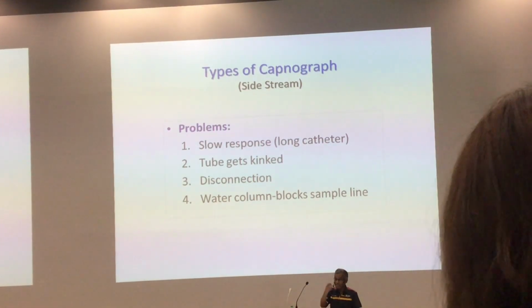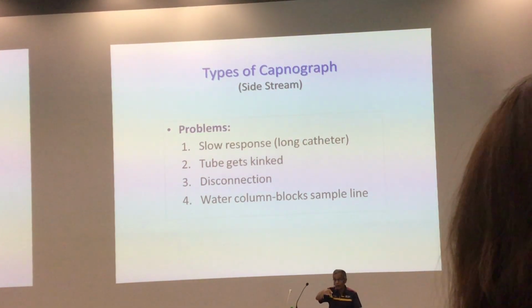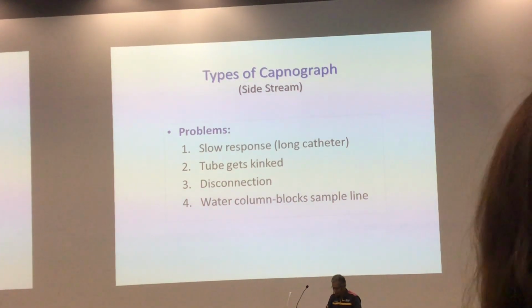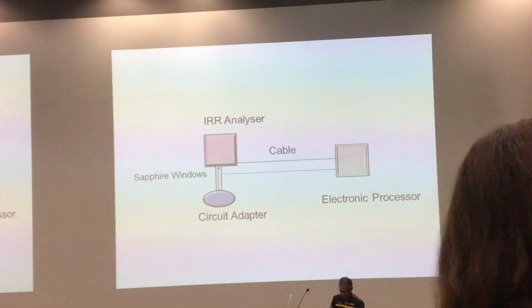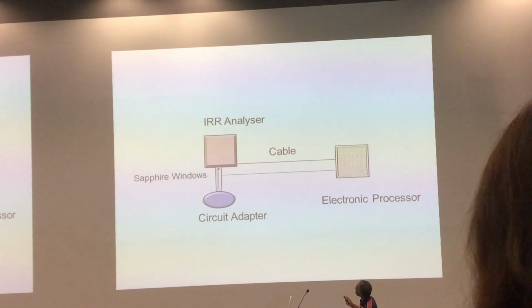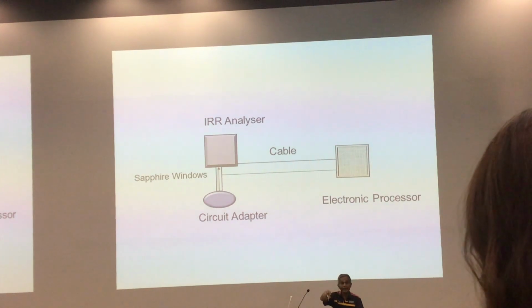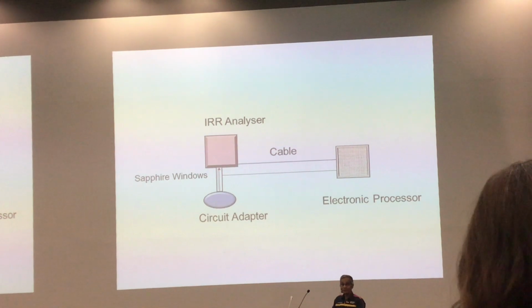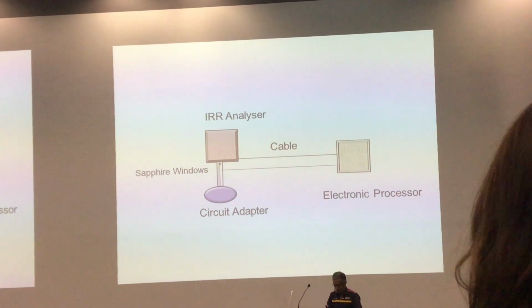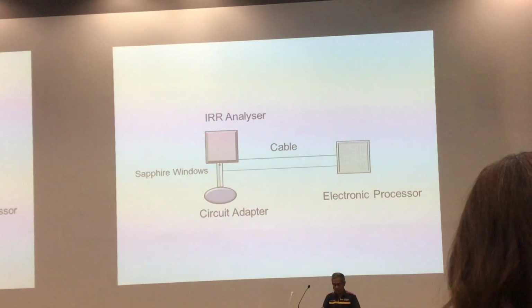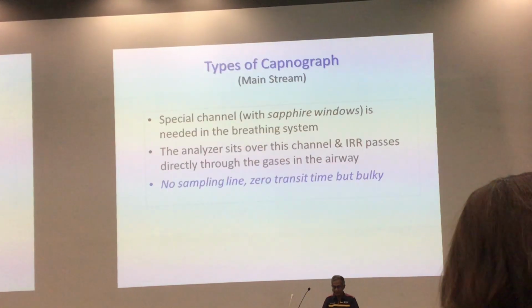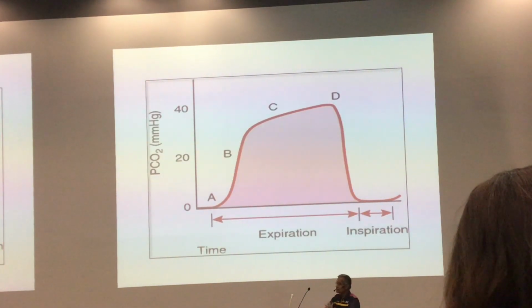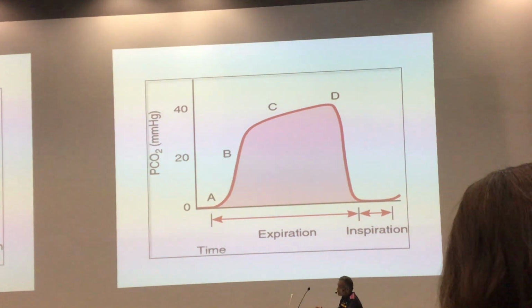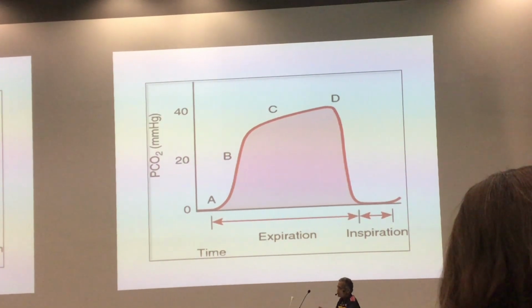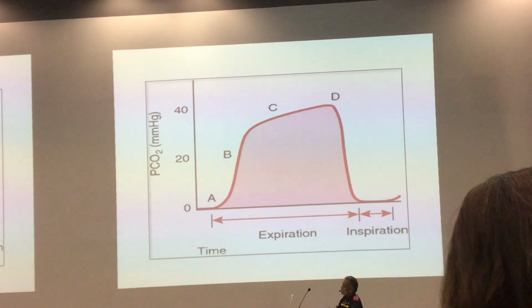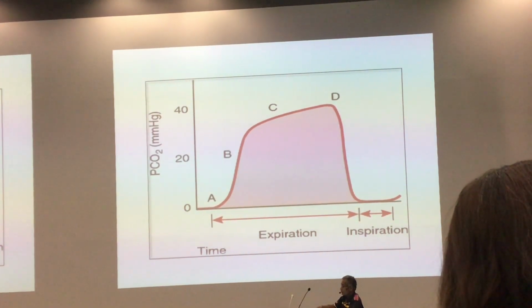If you use the mainstream capnograph, you get the response of CO2 immediately, right? This is the mainstream, which means the CO2 analyzer is attached to the patient at the Y-piece. It's sitting there, right? So it will analyze there without using a sampling line. So the response is within 5 seconds, you get the CO2 waveform already. This is the difference between side stream and mainstream. In terms of response, maybe we don't bother very much, because what is the difference between 5 seconds and 30 seconds, right? The patient won't die because of 30 seconds. So you can still get the capnograph 30 seconds later compared to 5 seconds.